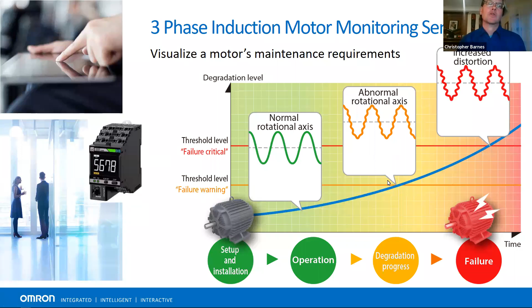We're also now going to look at the current analysis ones, and what they would pick up. You can see normal operation, a nice smooth sine wave, and then as you have issues or degradation, you see distortion in the sine wave. That can be picked up by looking at the data with some current transformers. You can see that pattern. So you put a current transformer, or CT, on here. This basically shows you the load. When it's operating healthy or normally, this is what it would look like, and as it gets distorted, it's during abnormal operation.